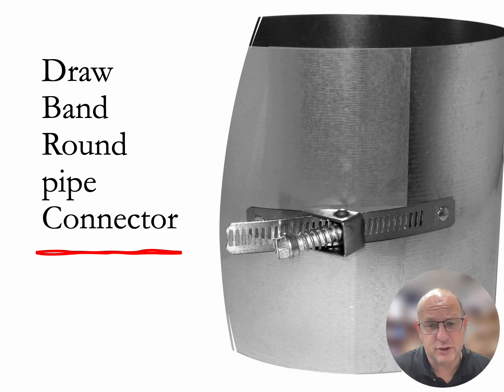If you're doing this correctly, you'll never have to use one of these within our systems, but you might have to in some cases where the pipe is hard to bend into the position that it is, or somebody nailed the boot in there, and it's going to be impossible for you to get that boot off so that you could stick it up within the piping itself. We can use a drawband pipe connector on our systems, and you should be good to go with air tightness. And also with this, we're going to mastic it up. Put that caulk on a brush around this as well to create that airtight seal for our ductwork itself.